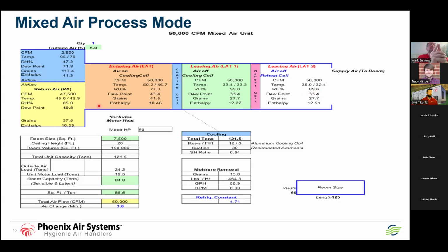So here's the air in the cooling coil, comprised of 3 things. It's the blue outside air. It's the yellow return air. Typically on these, we like to use what we call a blow-through configuration. What does that mean? That means that the motor is before the cooling coil. A 50 horsepower motor in this example will have 12.5 tons all by itself. You're going to raise the blended temperature of the outside air and the return air 2.5 to 3 degrees. So the air on the cooling coil is 50.2 and 46.7.